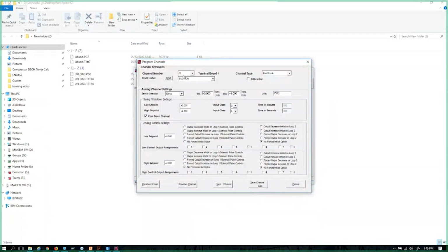In this case, we can see that channel 1 is my suction, what I'm calling suction pressure. I know it's pressure based on the PSIG units over on the right-hand side. For those of you who've been using the DE products for a long time but might be new to the enhanced DE-3000, this is a key critical change that's occurred. I'll skip ahead for just a minute and save channel data.